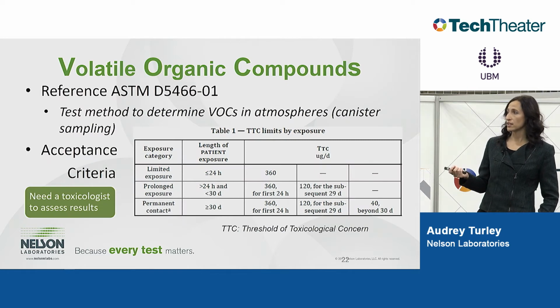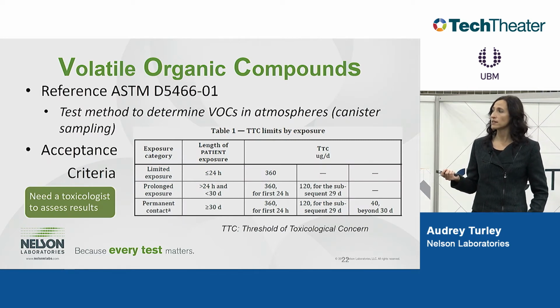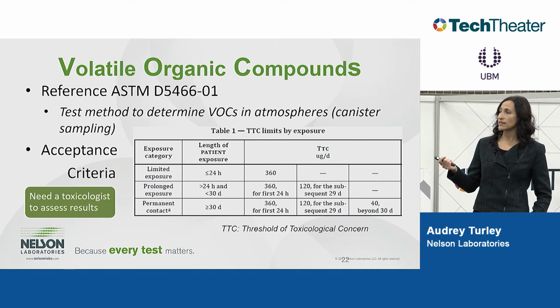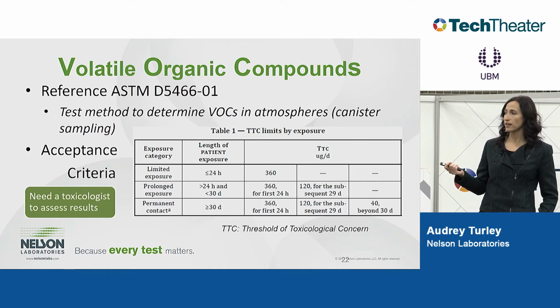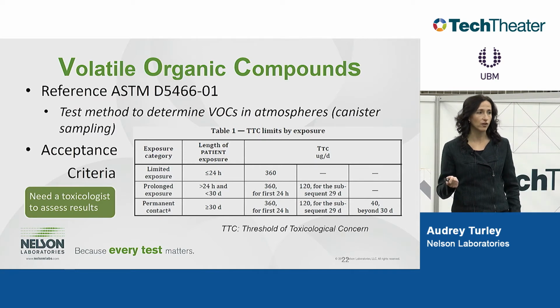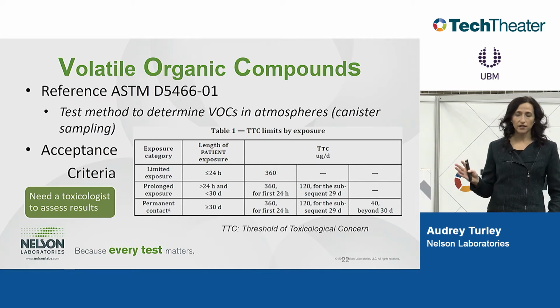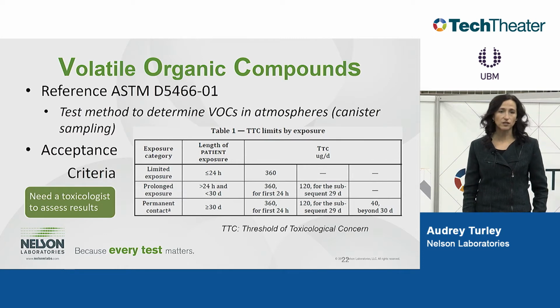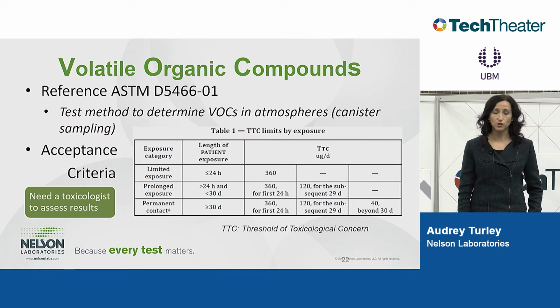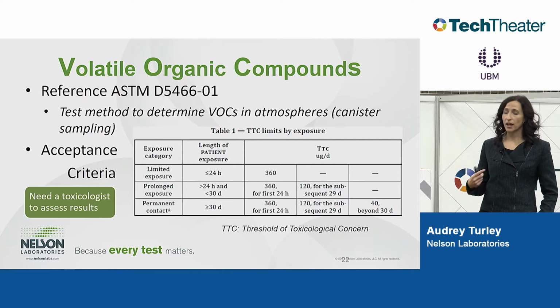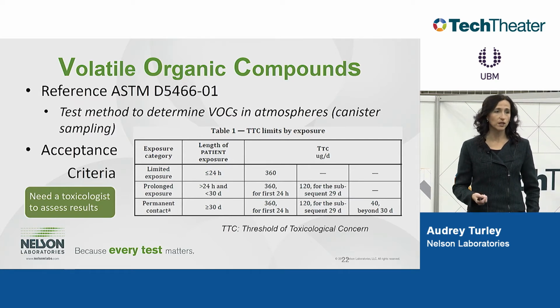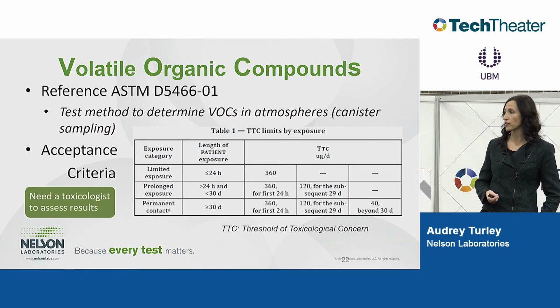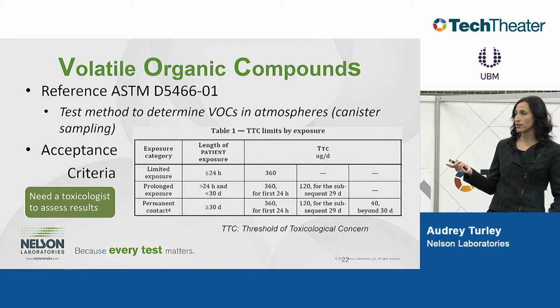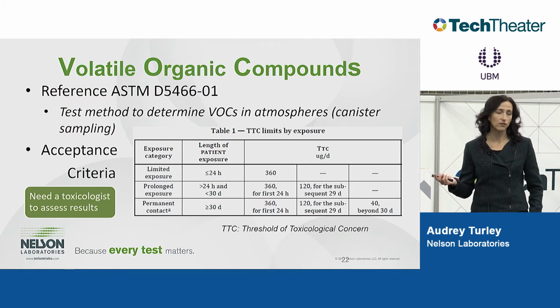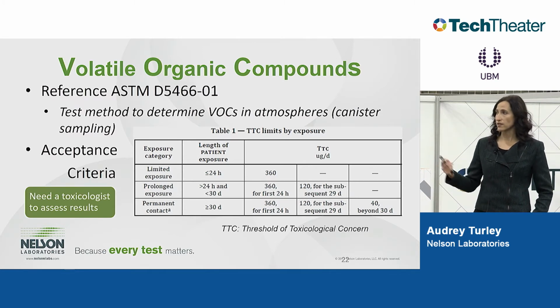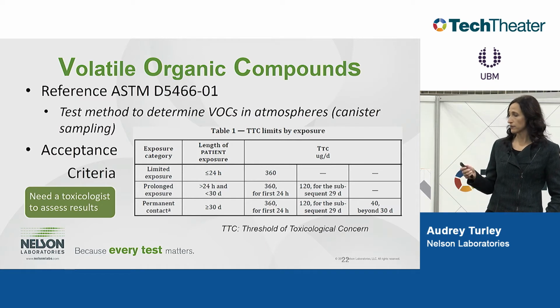In the guidance document, it does reference to use ASTM D5466, and then it states these acceptance criteria, which are based on the threshold of toxicological concern. So I just like to take this time to point out that you really need a board-certified toxicologist to assess and interpret these results, so that you're applying these thresholds appropriately. And we'll go through some of the calculations so that can be made a little more clear further on. But these acceptance criteria are based on breathing rates; default breathing rates are published in Part 1 of the 18562 standard that they're basing these off of.